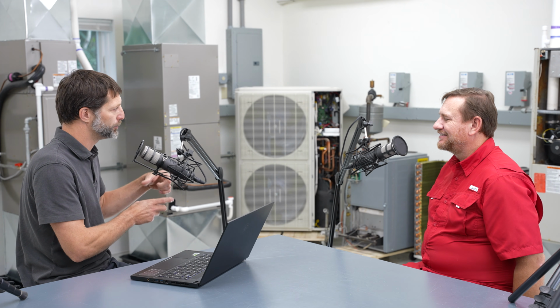One more thing is you need to be aware of what version of furnace or type of air handler you're looking at. Some air handlers don't even have a circuit board inside, some do, some are powering a PSC motor. The circuit board design a lot of times is based on what type of blower you have, so you need to pay attention and understand what's going on. It takes some component identification.